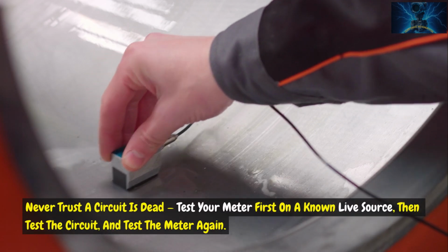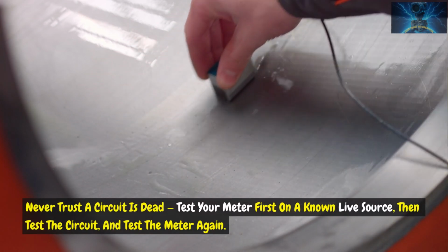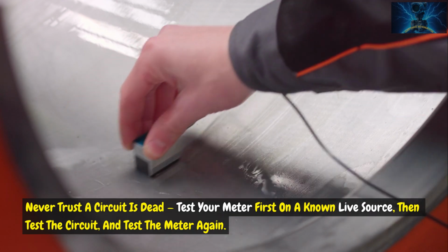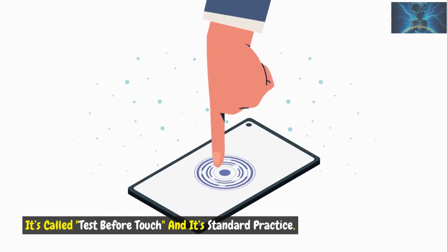Never trust a circuit is dead. Test your meter first on a known live source, then test the circuit, and test the meter again. It's called test before touch, and it's standard practice.